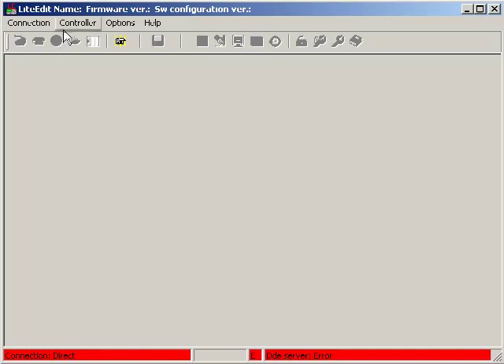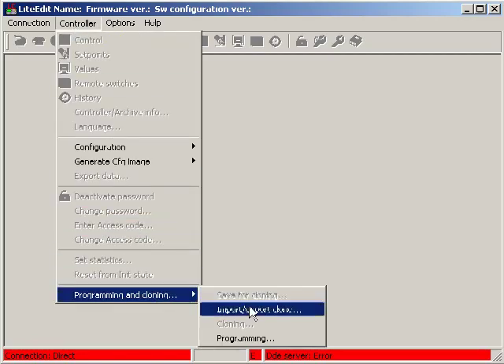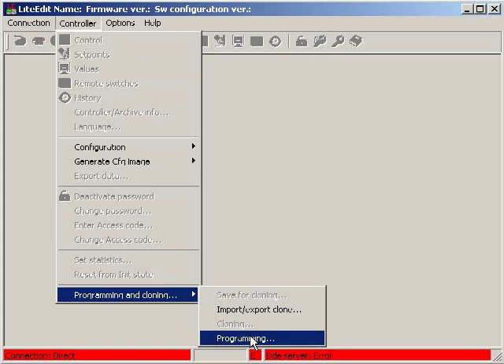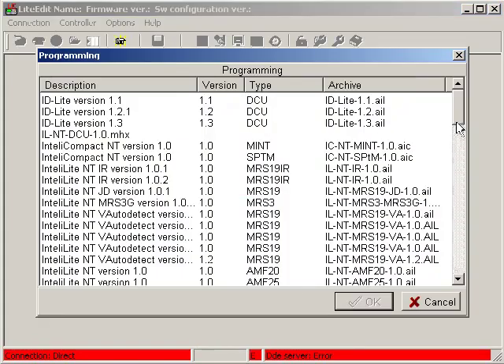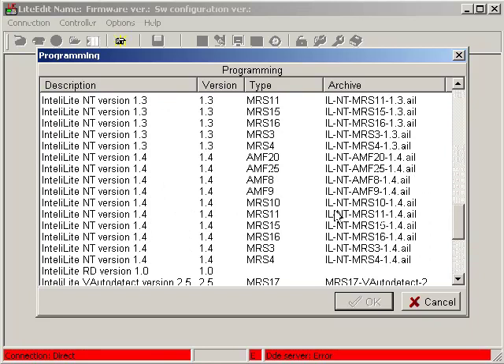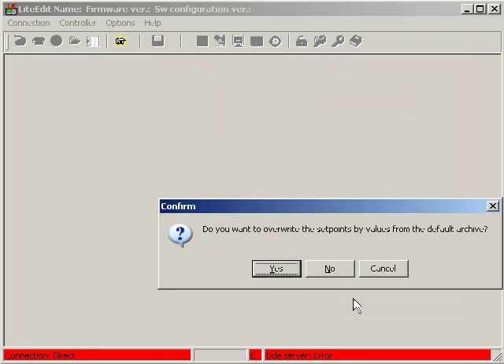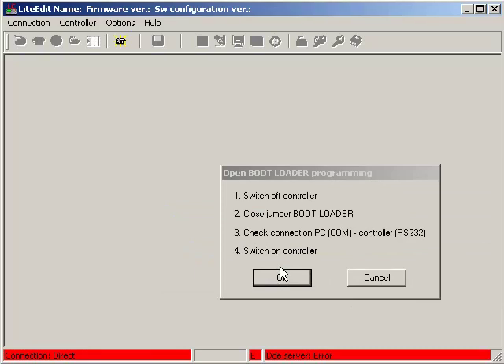It means that I need to program my controller using the boot jumper. I am going to programming and I am just about to select the right firmware for my ILNT AMF25 controller. I would like to overwrite setpoints by values from the default archive. LiteEdit is not able to program the unit, and it means that programming using the boot jumper is necessary.